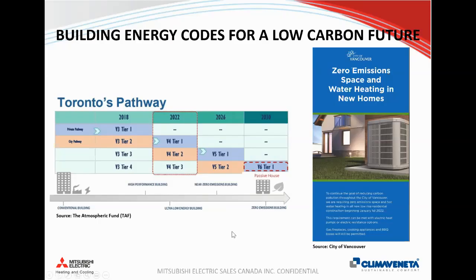And if the way we've always heated our buildings is with natural gas, either furnaces or boilers, if we're trying to get natural gas out of the buildings, the only way we can do it is with electric resistive heating and with a heat pump. But a heat pump, because of the COP, will always make sense over an electric boiler.